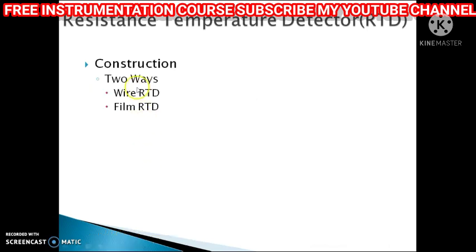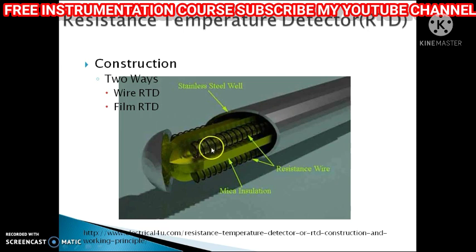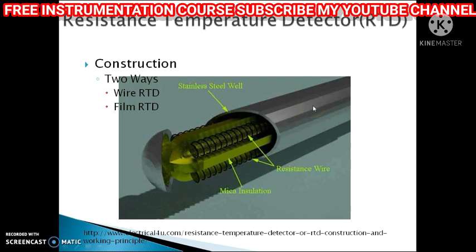Let's look at the construction of RTD. There are two ways in which they are manufactured: the wire RTD and the film RTD. The wire RTD is the classical RTD proposed by C. H. Meyers in 1932. It has a helical coil of platinum wound on a crossed mica base. The mica is used for electrical insulation. It was initially covered with a glass capillary, but nowadays it is covered with a stainless steel capillary which withstands high pressures.